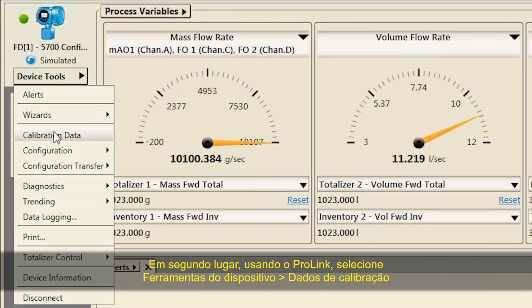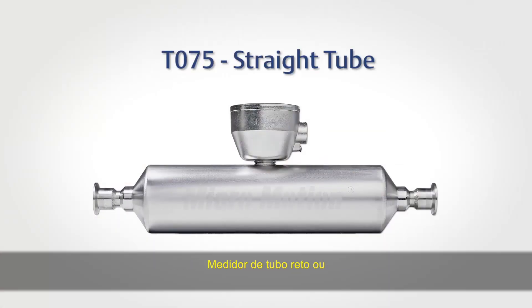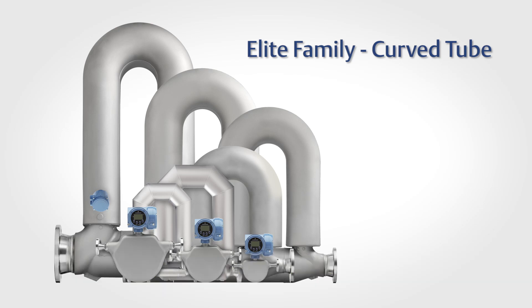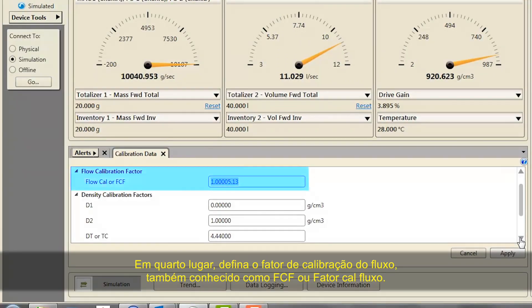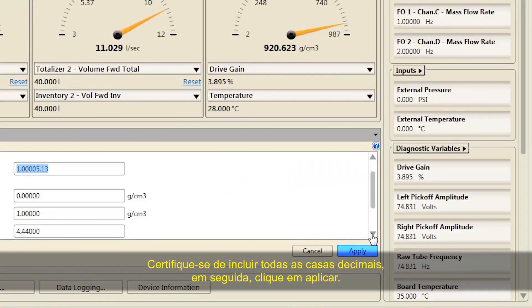Second, using ProLink select Device Tools, Calibration Data. Third, confirm your sensor type: straight tube meter or curved tube, which would be all sensors except a straight tube meter. Fourth, set the flow calibration factor, also known as FCF or flow cal factor. Be sure to include all decimal points and then click Apply.